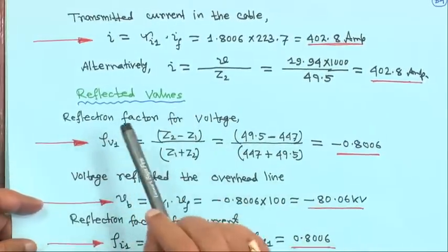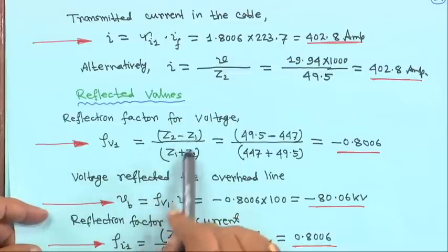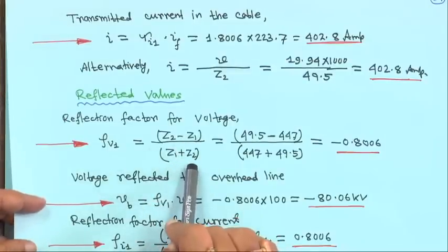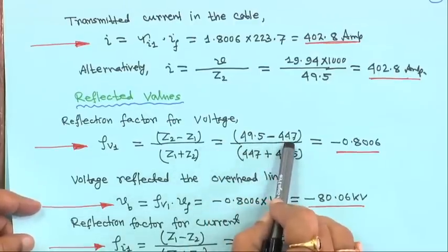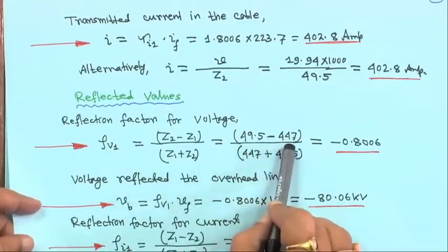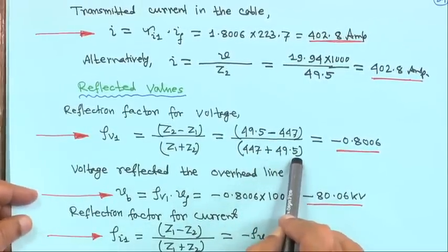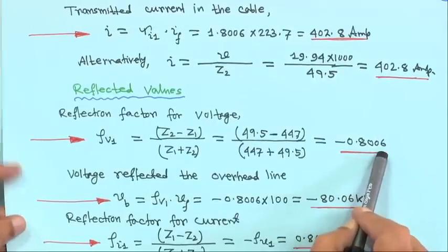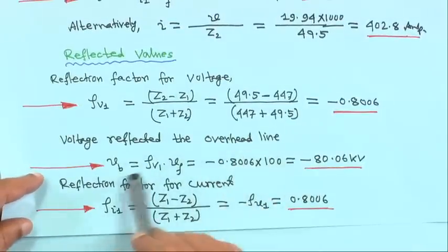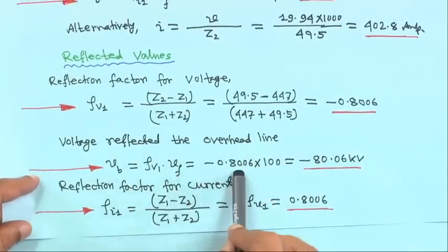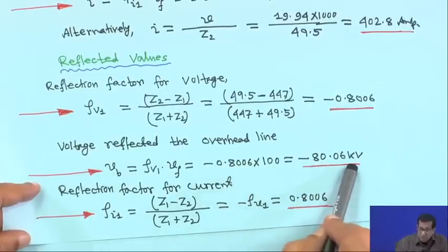For reflected values, the reflection factor for voltage is rho_V1 equals (Z2 − Z1) upon (Z1 + Z2). With Z2 equal to 49.5 and Z1 equal to 447, that gives (49.5 − 447) divided by (447 + 49.5), which equals minus 0.8006. Therefore, voltage reflected in the overhead line, Vb, equals rho_V1 × Vf, which is −0.8006×100 kV, giving −80.06 kV.